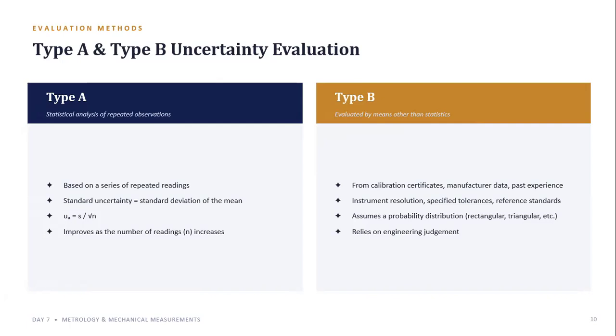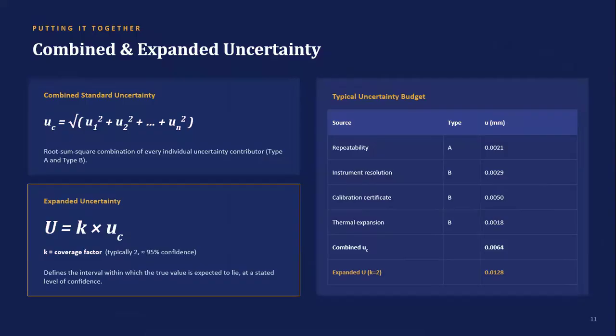The type B uncertainty is evaluated by methods other than statistical analysis of repeated observations. Sources may include calibration certificates, manufacturer specifications, previous measurement experience, instrument resolution, specified tolerances, and reference standards. Engineering judgment and appropriate probability distributions may be used in type B evaluation. Once the individual uncertainty components have been evaluated, they must be combined. The combined standard uncertainty is calculated by combining the individual uncertainty contributions using the root sum square method. The presentation expresses the following equation as illustrated below. The combined uncertainty may include contributions from both type A and type B sources.